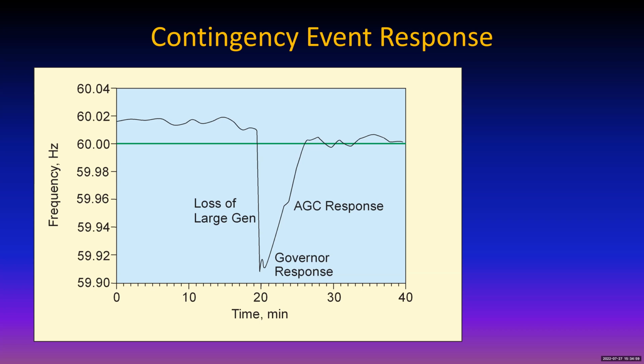What happens on all the fossil machines, the rest of them, is they have a governor that maintains your speed. As your torque requirement increases, as your power requirement increases, your fuel increases. That's what your governor is all about, maintaining the speed. It's like stepping on the gas to maintain speed while going up a hill.